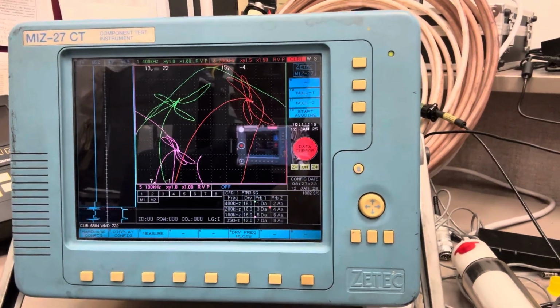Then we analyze the data and make recommendations to the site, which is me, as to what tubes are damaged, what tubes are okay, and what tubes need to be plugged, meaning taken out of service, or potentially repaired using things like sleeving, or re-rolling the tube expansion joints.